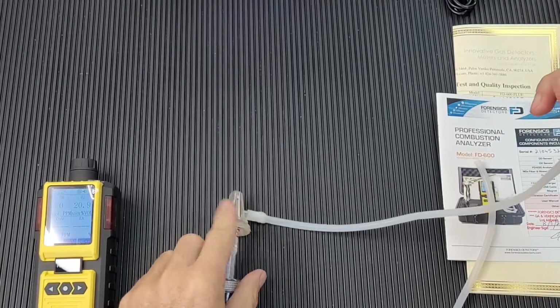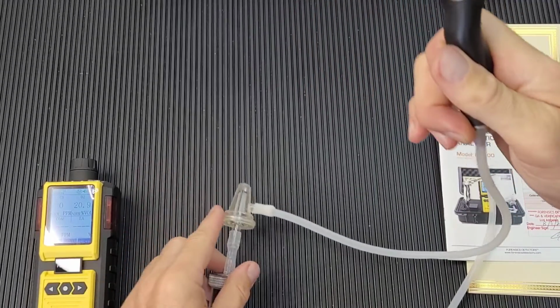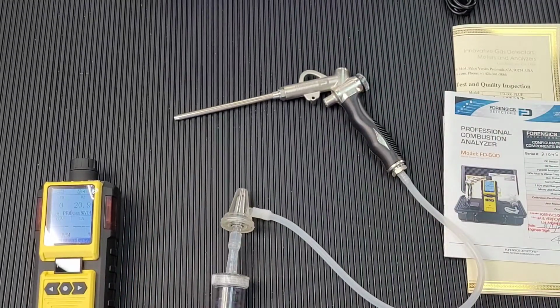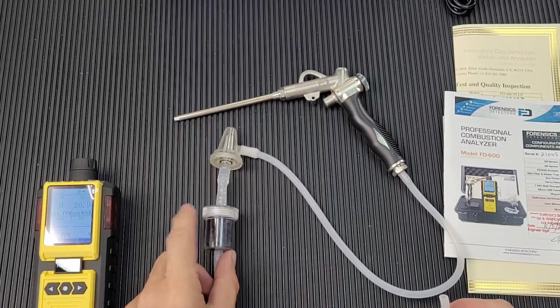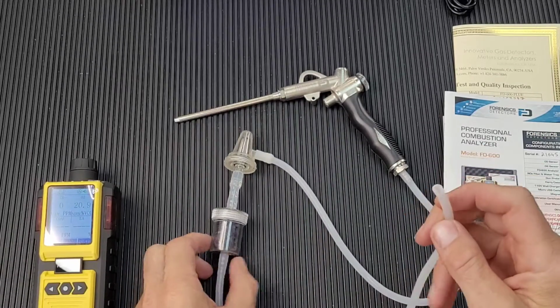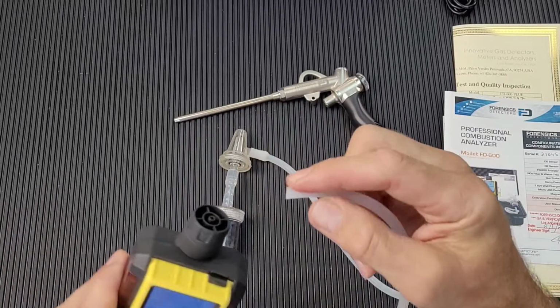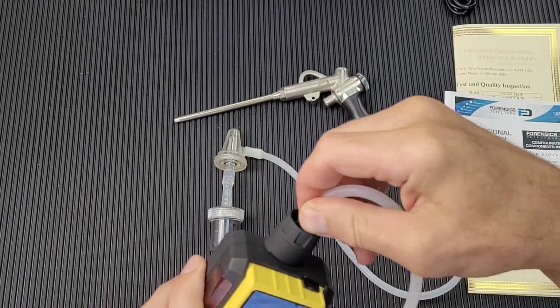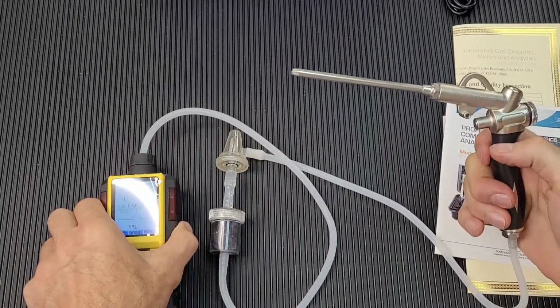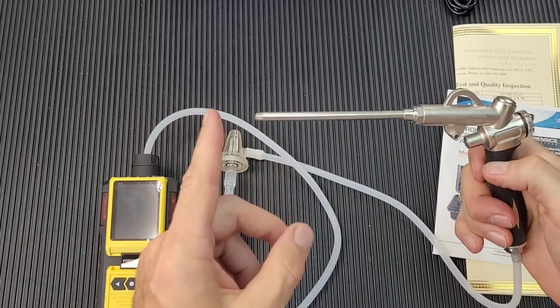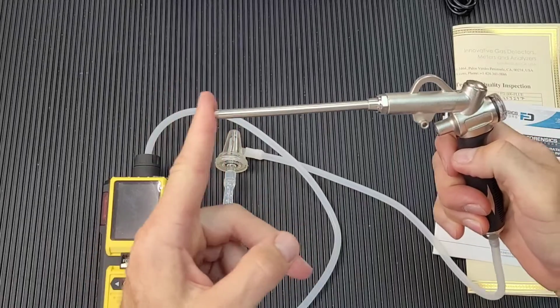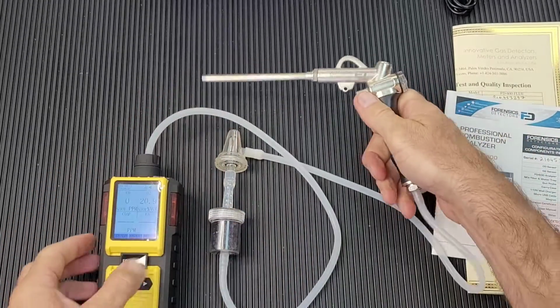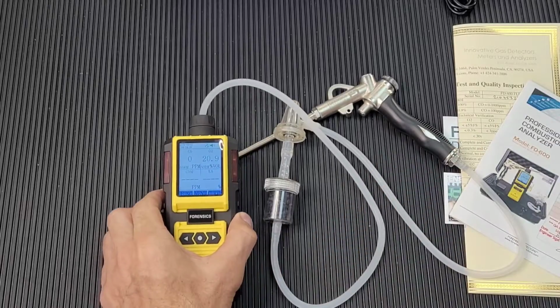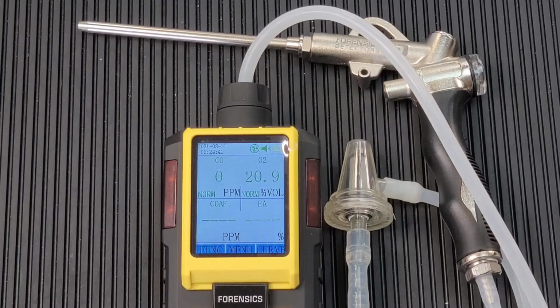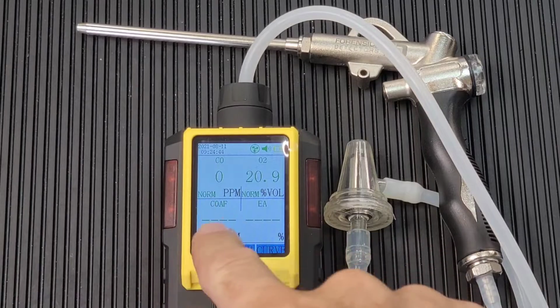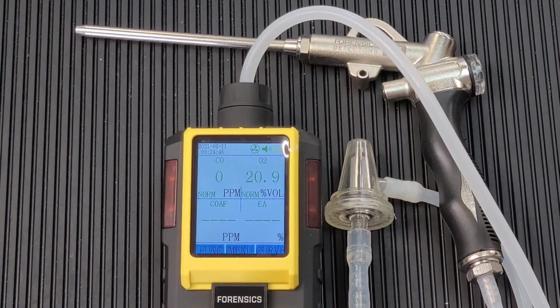It connects onto the end of the water trap, okay? It grabs all that condensation coming straight from the flue. And on the other end, the gas goes through the filter here with charcoal and moisture pellets. And then the other end goes onto the analyzer. And that's the way it works, okay? That's the kit. I emphasize again and again, make sure every connection is good. You could block it and you could see the resistance of the pump, okay? Now, we've turned this guy on. And let's zoom in a little bit here. Okay, we've zoomed in, we've turned it on, and as you could see, carbon monoxide 0, oxygen 20.9 ambient, and this is our Model 600.